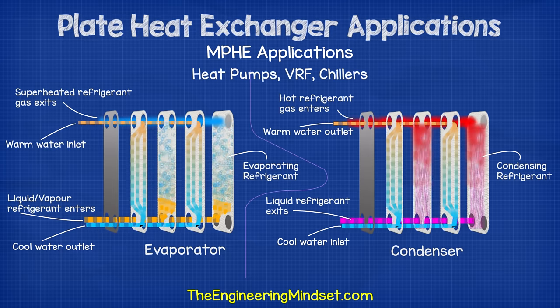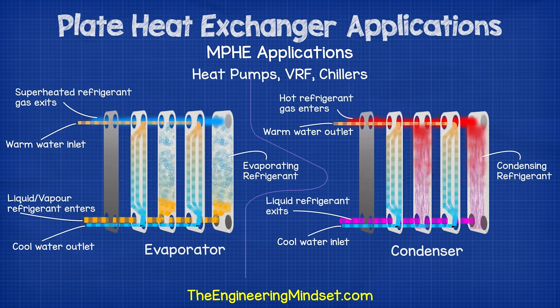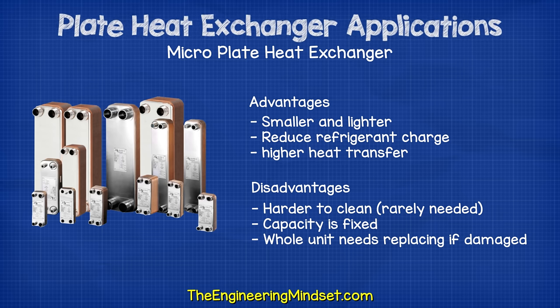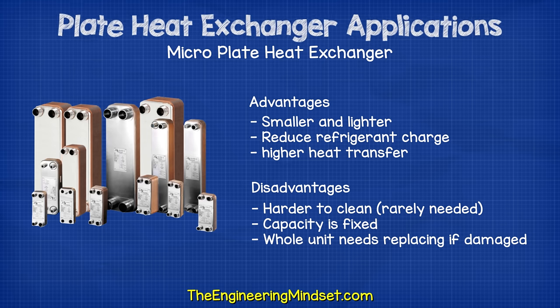Applications for micro plate heat exchangers include heat pumps, VRF units, and chiller evaporators and condensers. The pros are that they are lighter and smaller, have a reduced refrigerant charge, and have a higher heat transfer efficiency. The cons are that they are harder to clean, though this is rarely needed due to the fluids used and the turbulence of the design. For the brazed plate type, the whole unit must be replaced if damaged, and you cannot increase or decrease the capacity.